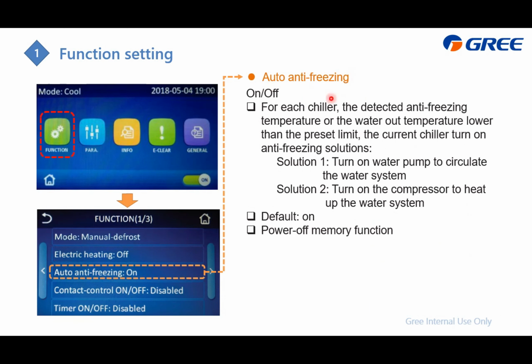Auto anti-freezing. When you turn on this function, it means that when the chiller detects that the anti-freezing temperature from the sensor, or the water out temperature, is lower than the preset value, the chiller will turn on the anti-freezing solutions. Solution 1 is to turn on the water pump to circulate the water system, and solution 2 is, when we detect that the water temperature is still going down, to turn on the compressor to heat up the water system.